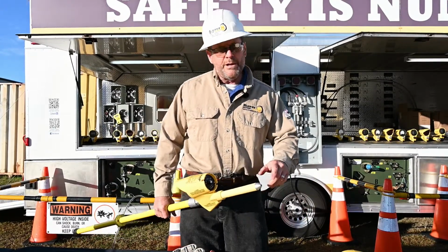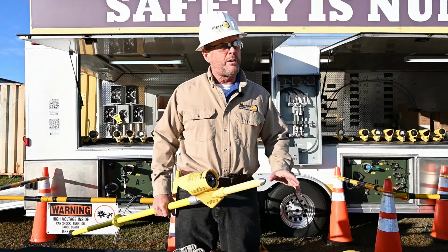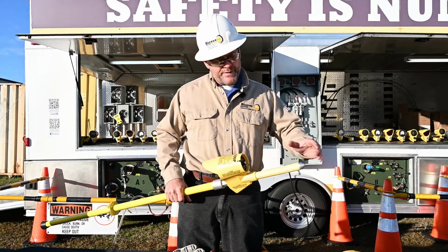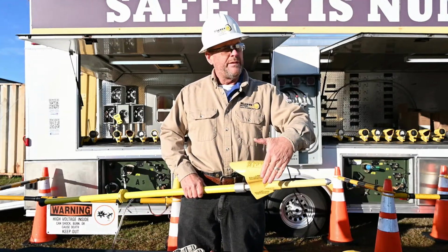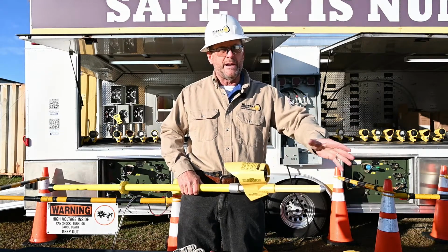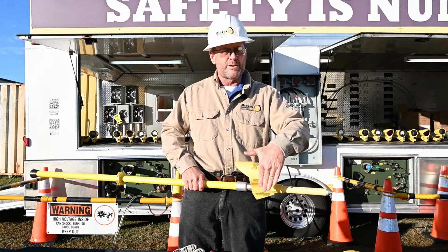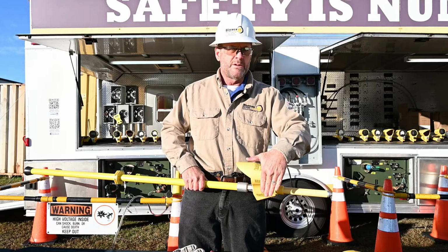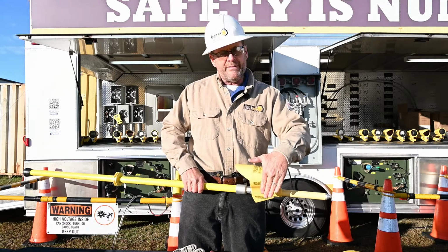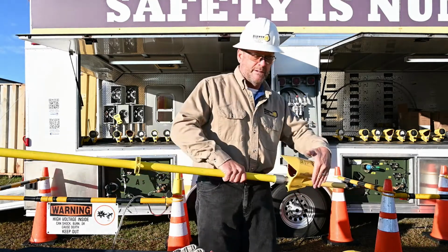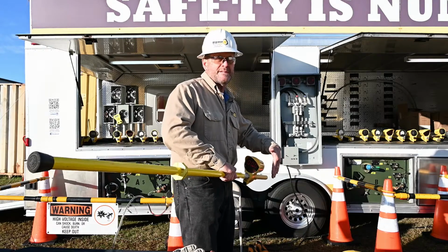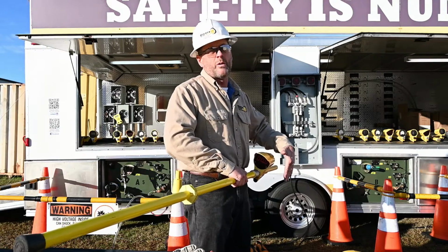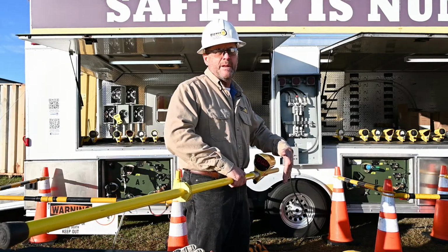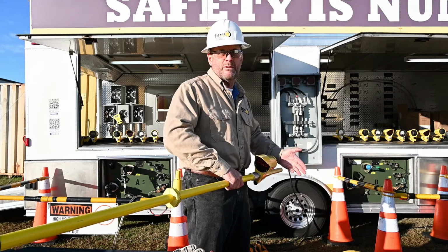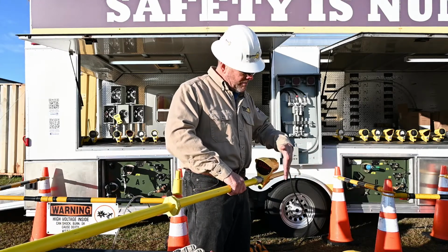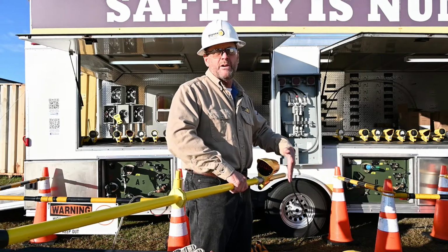So it's important when using these tools to always remember that tool is energized. If you visually inspect your work area and have a ground plane in close proximity to that meter, you have a high potential of an arc flash. That's pretty obvious because now you know how these tools work, corded or wireless - it's the same, the tools are energized. They have to be in order to work for you. So you do not want to have another potential, another hot phase nearby.